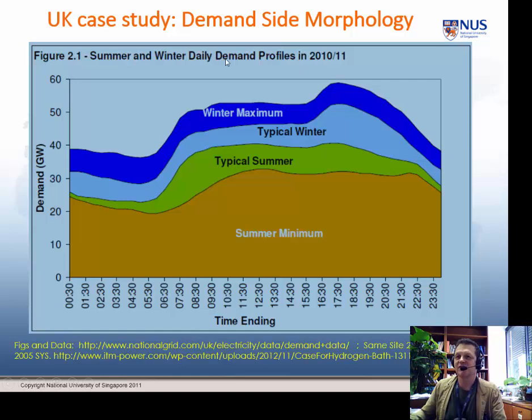And this is a sketch graph. Remember, the UK is temperate, summer and winter, so winter demand is higher than summer demand, because obviously in those climates you need to heat, although as climate begins to change, there is beginning to be a summer air conditioning demand now, and that's certainly the case in other places as well. But this is, if you want, one day cycle. So this is from 12:30 to, well, no, to midnight. And so this is what we talked about, the daily shape of demand.